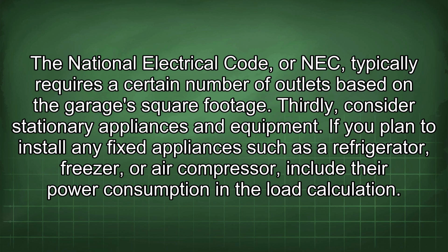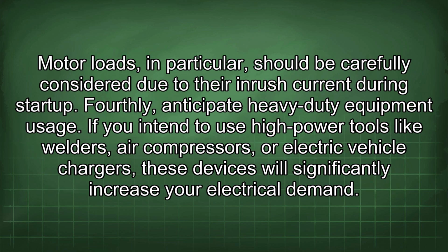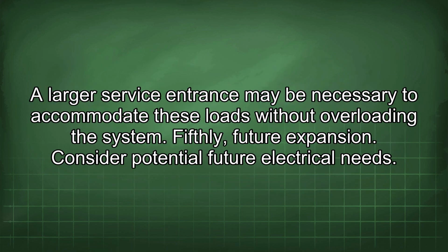Thirdly, consider stationary appliances and equipment. If you plan to install any fixed appliances such as a refrigerator, freezer, or air compressor, include their power consumption in the load calculation. Motor loads, in particular, should be carefully considered due to their inrush current during startup. Fourthly, anticipate heavy-duty equipment usage. If you intend to use high-power tools like welders, air compressors, or electric vehicle chargers, these devices will significantly increase your electrical demand. A larger service entrance may be necessary to accommodate these loads without overloading the system.